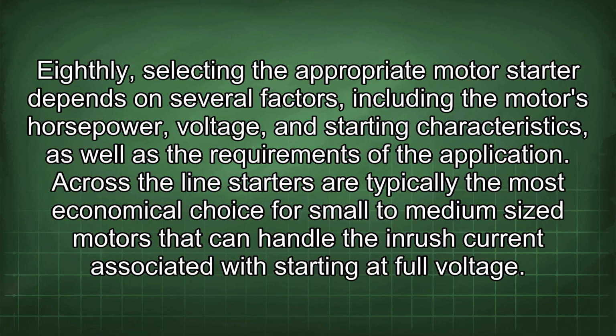Eighthly, selecting the appropriate motor starter depends on several factors, including the motor's horsepower, voltage, and starting characteristics, as well as the requirements of the application. Across-the-line starters are typically the most economical choice for small to medium-sized motors that can handle the inrush current associated with starting at full voltage.